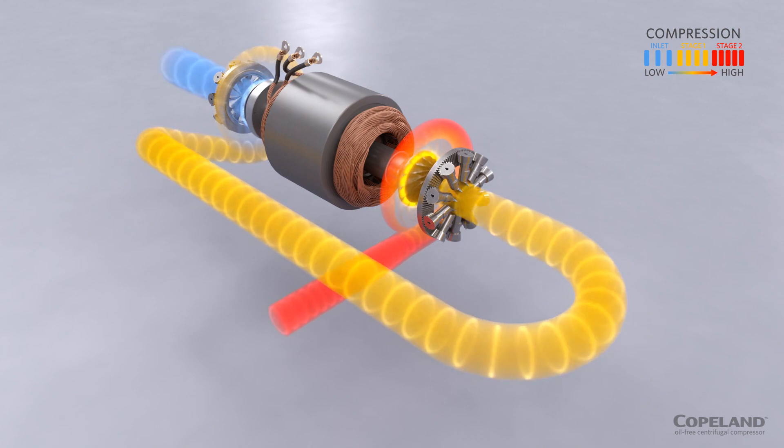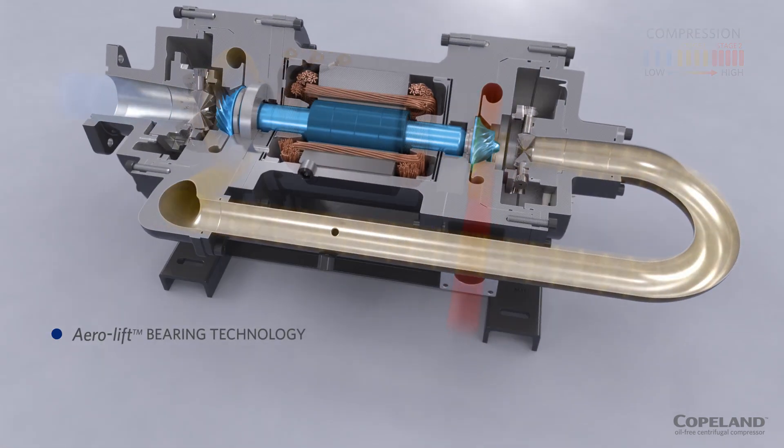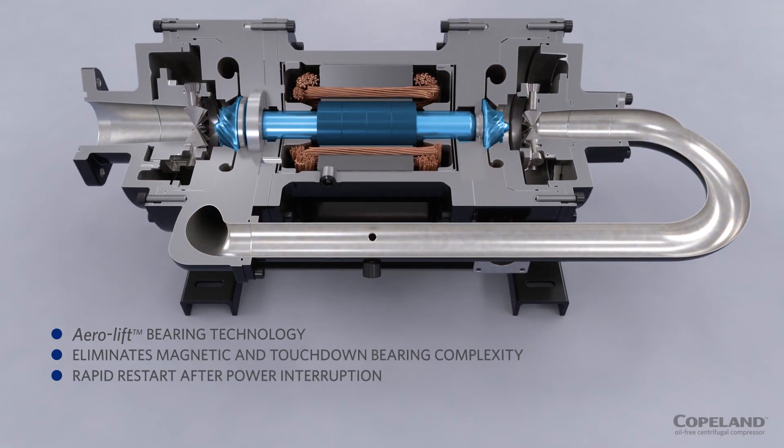While this process is similar to other centrifugal compressors, what really sets the Copeland Oil-Free Centrifugal Compressor apart is its innovative aero-lift bearing technology, which eliminates the need for complicated bearing control electronics and auxiliary redundant touchdown bearings found in other oil-free centrifugal compressors.